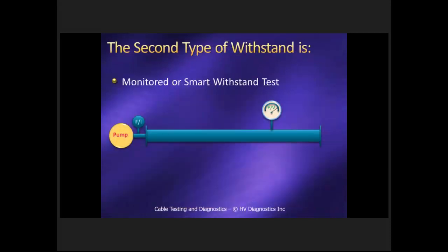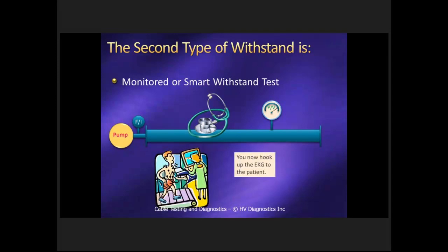Okay, so if we now look at the monitored type of test where we monitor a particular type of diagnostics, again we have the same water pump feeding into a pipe which is equivalent to our cable, and while we do this we actually now hook up a form of diagnostic onto the cable. What we're talking about there is partial discharge during application of voltage, or pressure in this case. So from a healthcare perspective, that's what I'm looking at now.